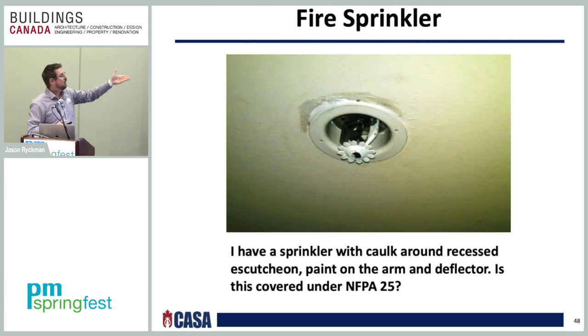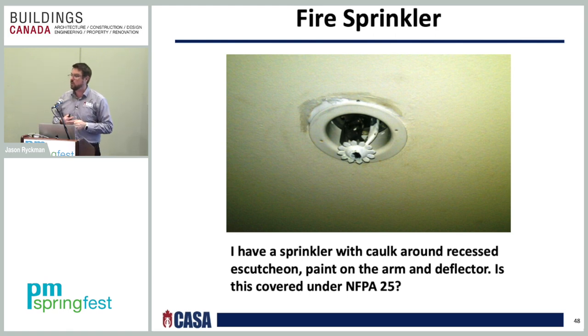that I gave some questions that you may have. So, fire sprinkler. I have a sprinkler with sound caulking on it around the recessed escutcheon, paint on the arms, and deflector. Is this covered by NFPA 25? Everyone should be shaking. Yes, it is. 5.2.1.1. It's considered a critical deficiency because ultimately there is paint on the deflector and also on the element itself. So the paint on the frame arm would be considered a critical deficiency, and paint on the element, the bulb, deflector, would be considered an impairment. Okay? So you have two problems there. You have critical deficiency and an impairment. So guess what? You got to fix it. No ifs or buts about it.